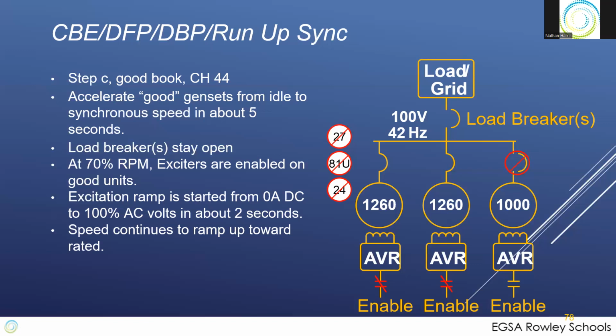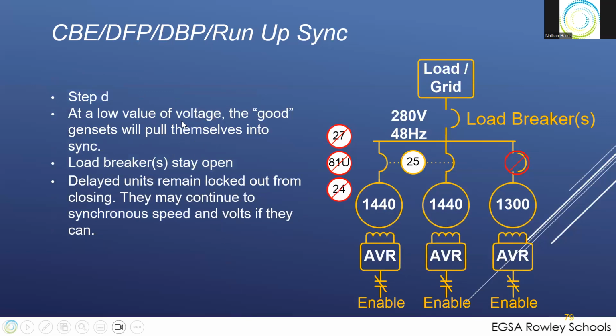And so it's ramping up. Your machines are accelerating, the fuel is being added, and the alternators are accelerating together. The breakers are closed, the excitation is coming on, and it pulls them into sync. It pulls them into sync and continues to ramp up towards rated speed. When you hit your value of voltage, the gensets put themselves into sync. The load breaker is still open now. Your AVRs are on, your generators are on, you're putting out voltage. You're not quite at full voltage yet, but you're coming up, your frequency is coming up, and the other units are locked out.